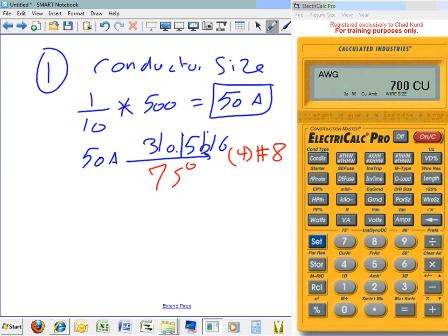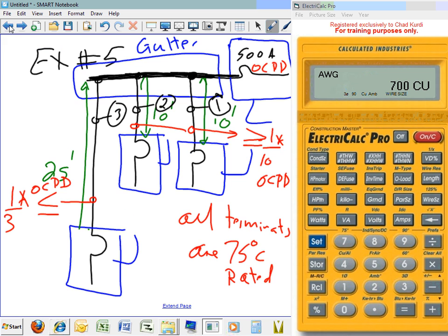Okay, let's use a calculator as long as we're on it. Well, before we do that, let's put the overcurrent protection device on it. This is just a conductor size, and the overcurrent protection device to land it on. It has to be 50, right? What's the next standard? Go to 240.6 and look at the 50 here. It's already a standard size, so we don't have to mess with it. It's 50. So this will be a 50 amp device, and we already calculated that conductor.